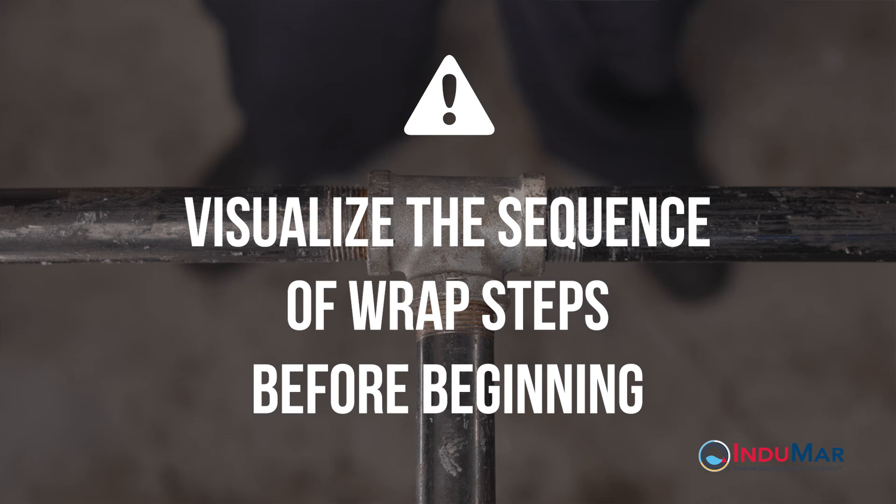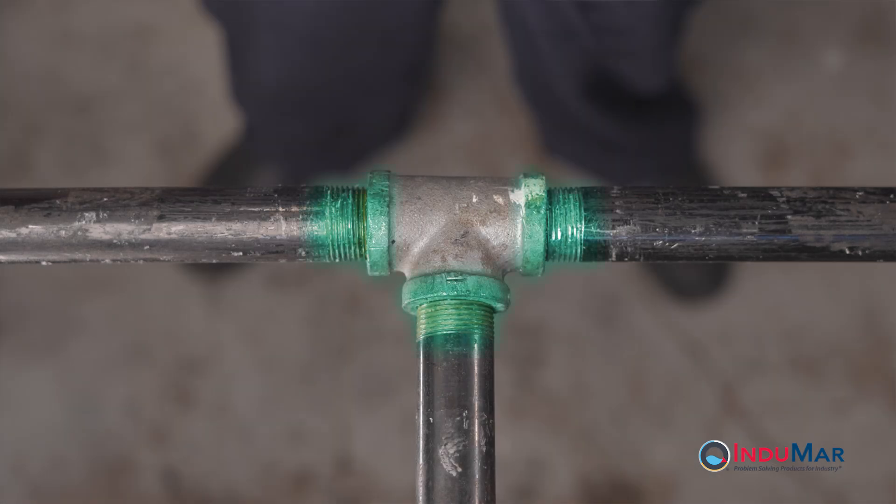Before beginning the wrap, it is important to visualize the general plan or sequence of wrap steps. This is aided by identifying two separate areas of repair. The first area is the pipe surface where it joins the tee — these areas, numbered one through three, will be wrapped circumferentially. The second area is the tee fitting body, which will be wrapped with a crossing pattern.